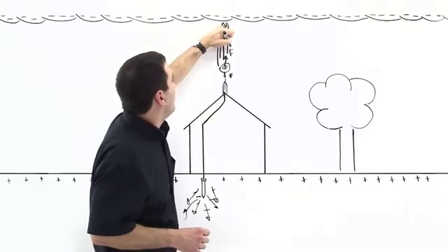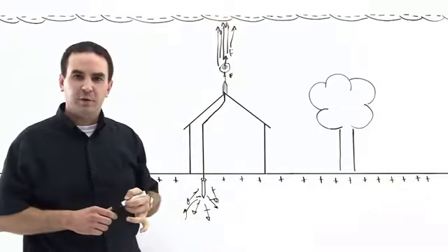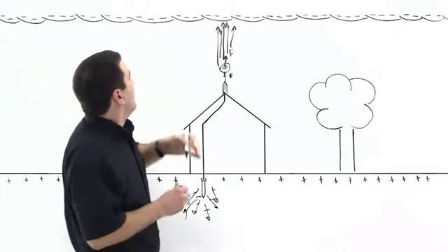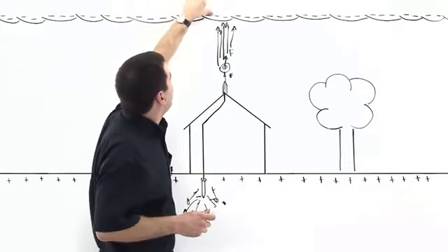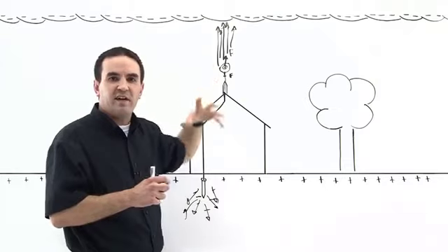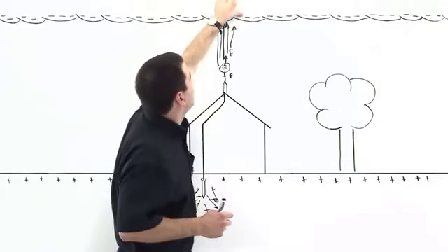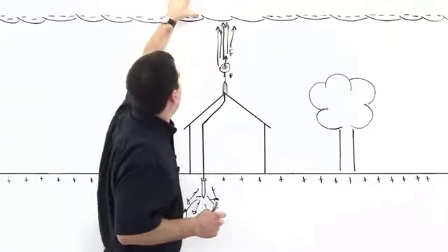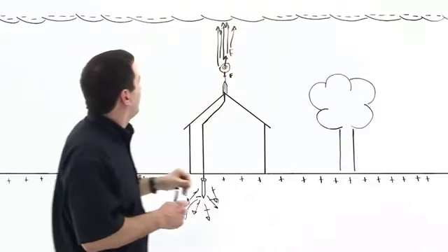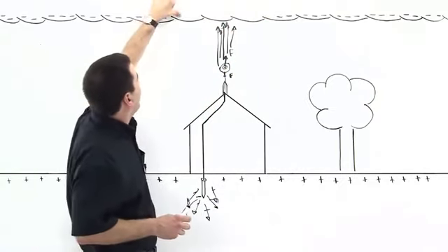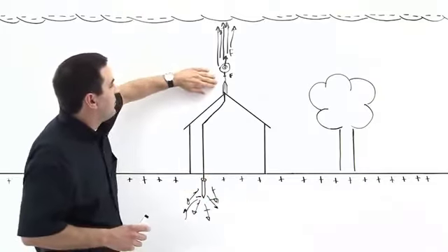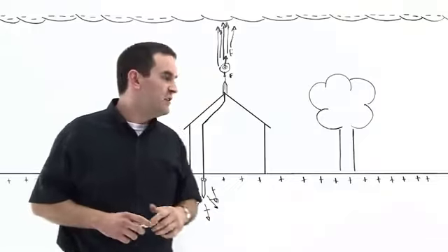An ion is any atom that has charge. This atom lacks electrons. It's not neutral anymore, so it's a positive ion. When these ions get up to the cloud, each ion will neutralize one of these electrons. So these ions will come up to the cloud and capture an electron, and so they're neutralizing this region of the cloud, right above the structure. So lightning rods not only do not attract lightning, they prevent lightning from striking structures because of this ionization process that's called coronal discharge.